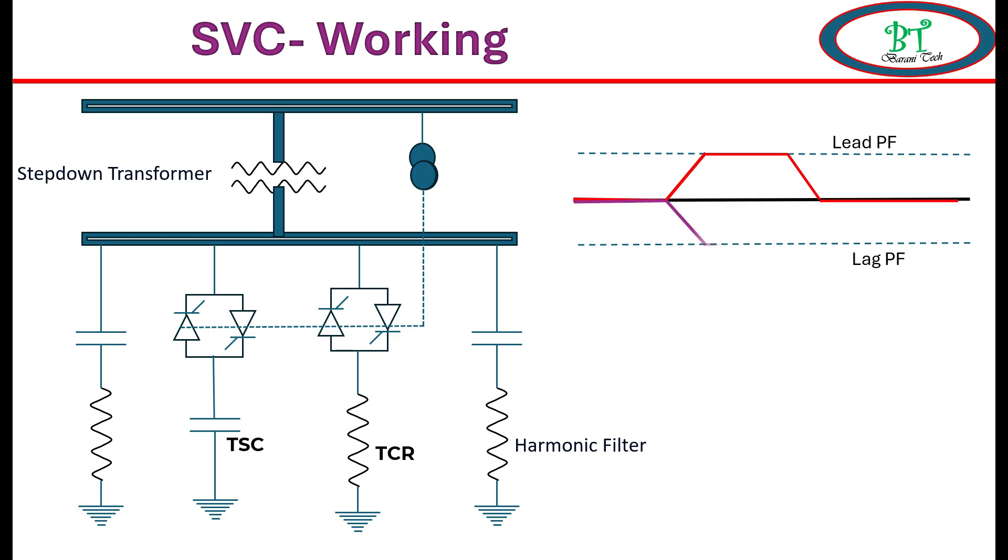On the other hand, if the power factor gets lagged due to high inductance load, during this time TSC will get on and increase the power factor. Once it comes to normal, then this switch will get turned off. From this, we can clearly understand SVC working with switching operation with the help of TCR and TSC with respect to the power factor.